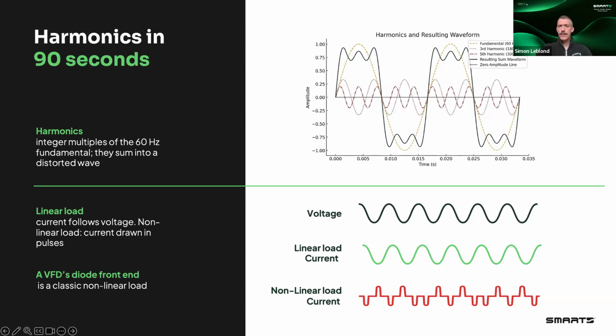And the VFD, because it's drawing current in this pulsing waveform, is what we call a nonlinear load. Another example would be an LED light driver, versus a linear load like a resistive heater or incandescent fixture, where you can really see that the voltage and line current are drawn symmetrically as a sine wave.